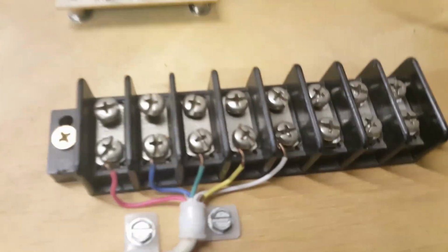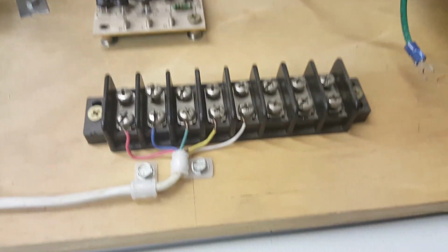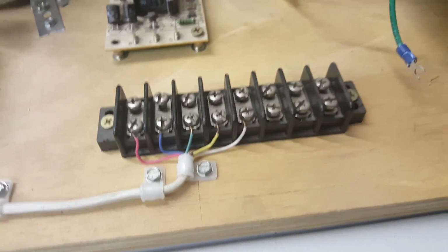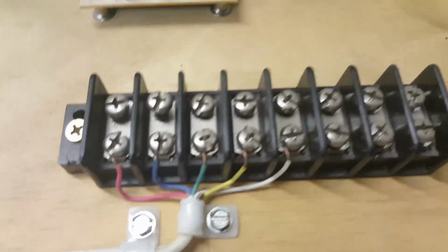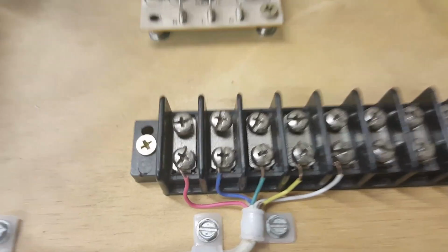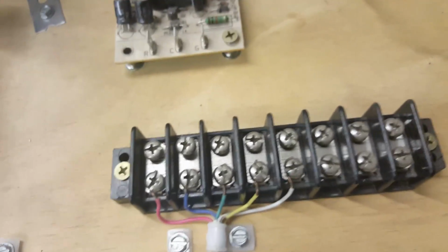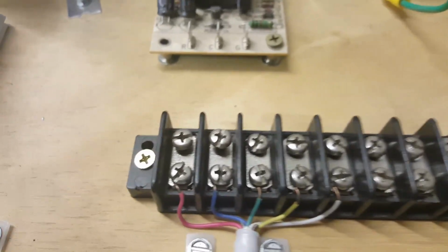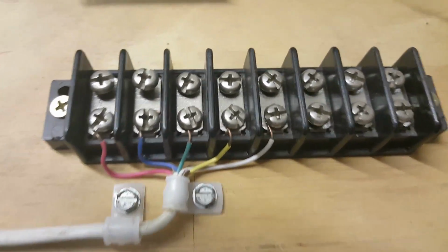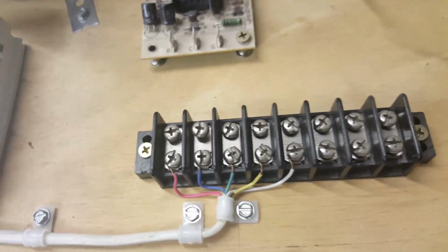The terminal board itself is a luxury of the system. We don't have to have it. It's not an operating control. It's not a safety control, but it gives us a place of termination, simplifies it, so we don't have to use so many wire nuts, and also it allows us to have a place of troubleshooting. Just remember that you don't always have those, and that it could be all wire nutted together.